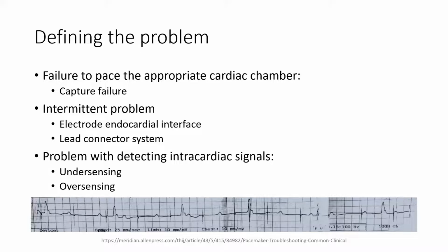The second may be due to inappropriate amplitude or slew rate of the intrinsic beat. And the third reason for undersensing is attenuation of signal by the electrical dysfunction of the lead or the pulse generator. A malfunctioning pulse generator can be caused by component failure in the electric circuitry or a defective reed switch which remains in the closed position. In both these cases, this will result in asynchronous pacing. Very importantly, in the analysis of ECG undersensing, oversensing producing asynchronous mode pacing due to interference should always be excluded first as the possible cause.